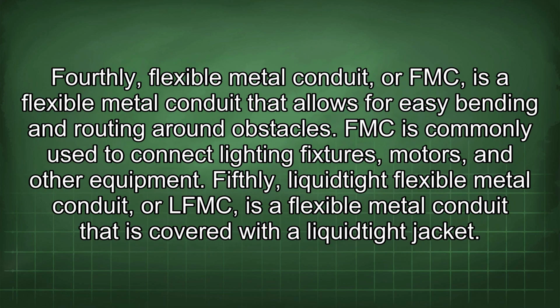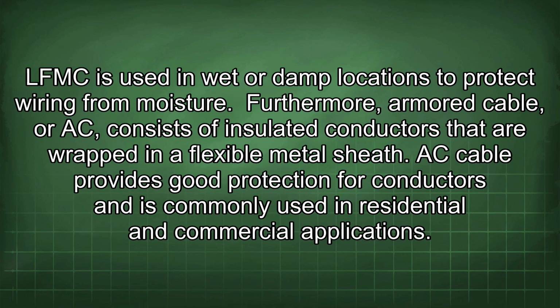Fourthly, flexible metal conduit, or FMC, is a flexible metal conduit that allows for easy bending and routing around obstacles. FMC is commonly used to connect lighting fixtures, motors, and other equipment. Fifthly, liquid-tight flexible metal conduit, or LFMC, is a flexible metal conduit that is covered with a liquid-tight jacket. LFMC is used in wet or damp locations to protect wiring from moisture.